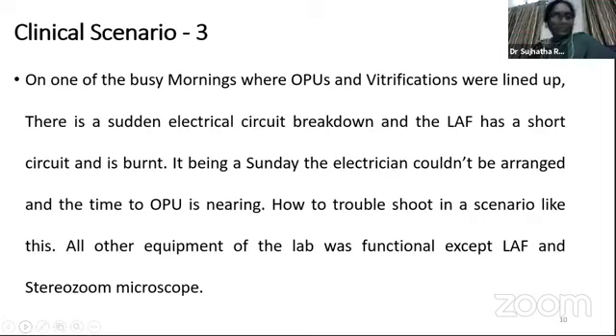But just compose yourself. First thing, check if it is localized to one particular plug socket. Even if your microscope is inside the laminar airflow, try to remove the plug of the stereozoom microscope and plug it in another power source. It should work. In case it doesn't work, it might mean that the bulb has gone because of this excessive power which has come. So change the microscope bulb and it will work.